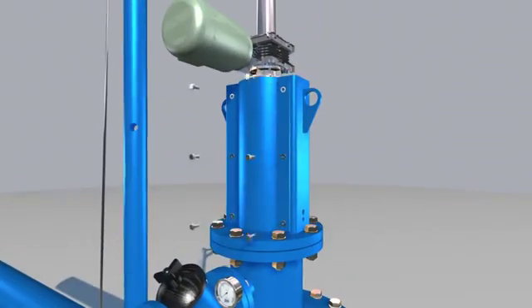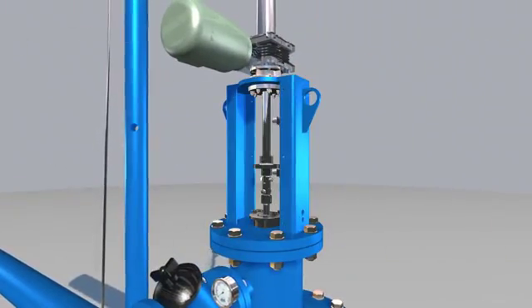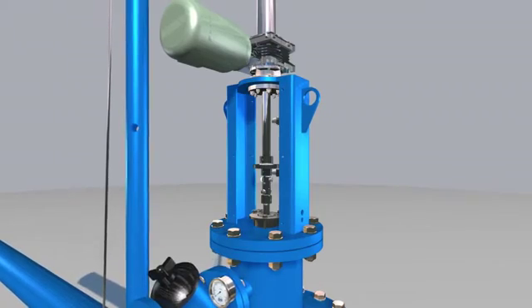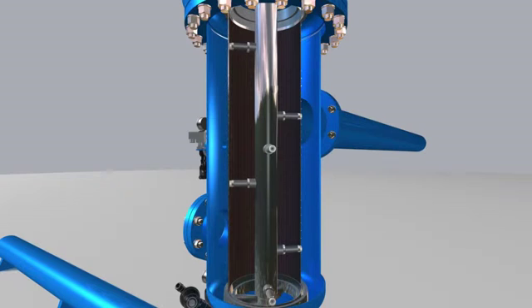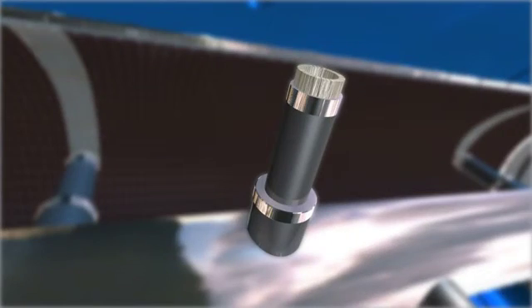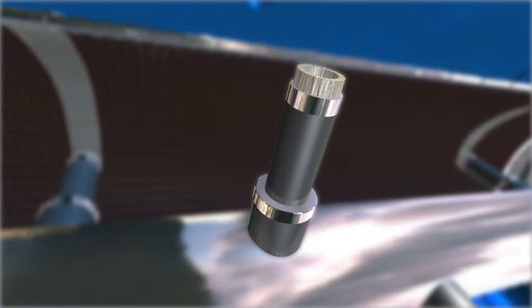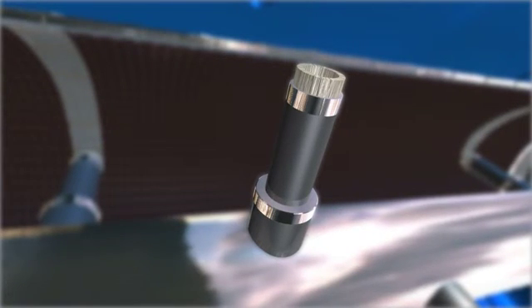When this value is reached, the differential pressure acts on the control panel that commands the opening of the drain valve, which is housed in the cleaning chamber, and the helical motion of the suction scanner, where the suction nozzles with nylon bristles, patented by STF filtros, are housed.